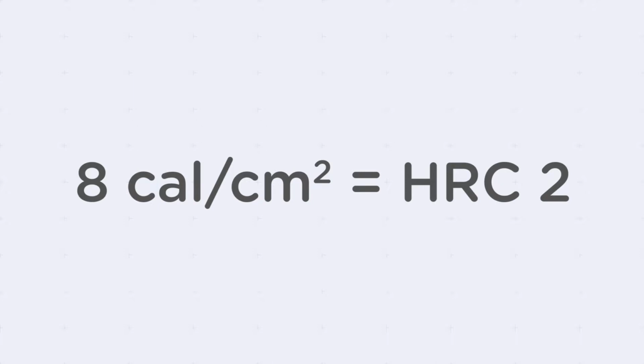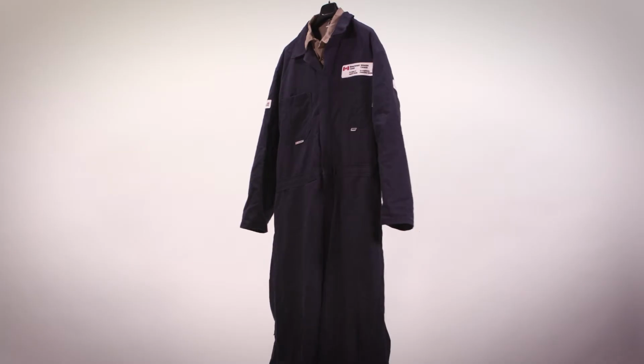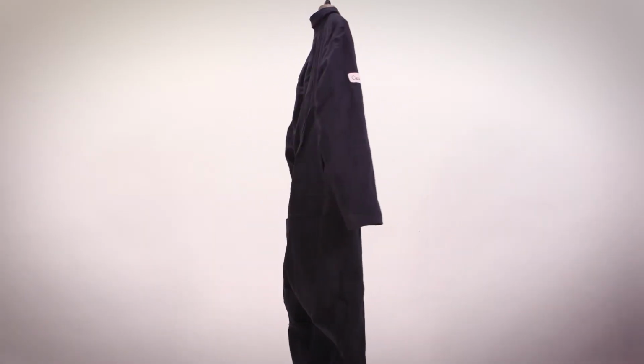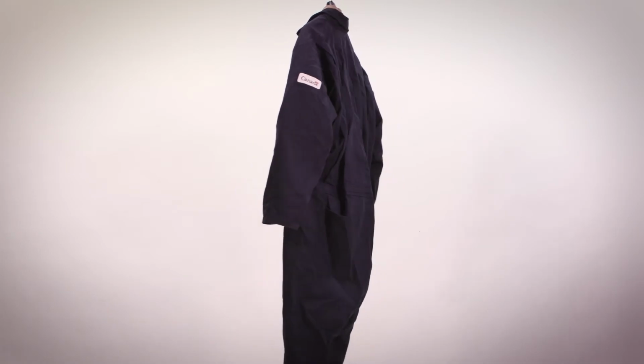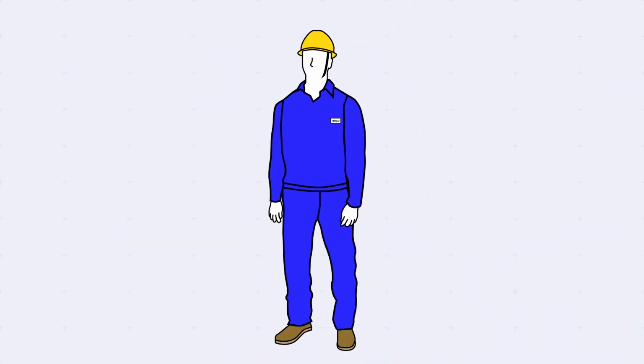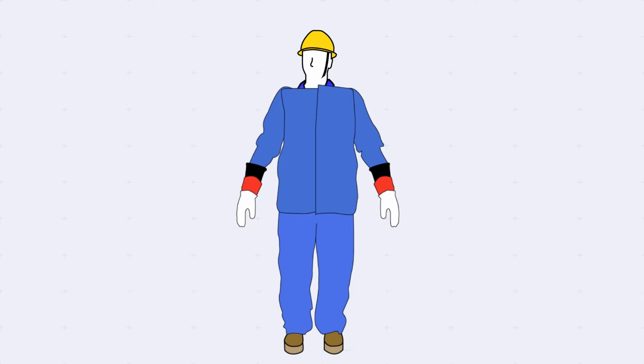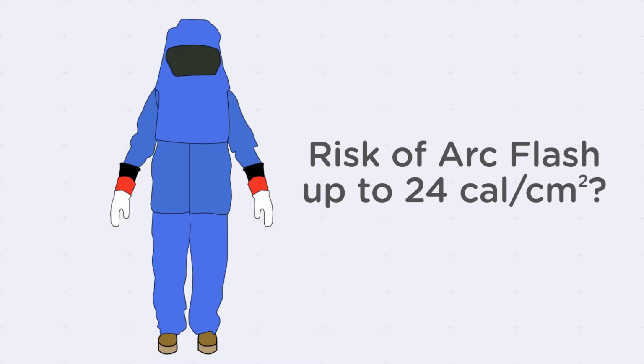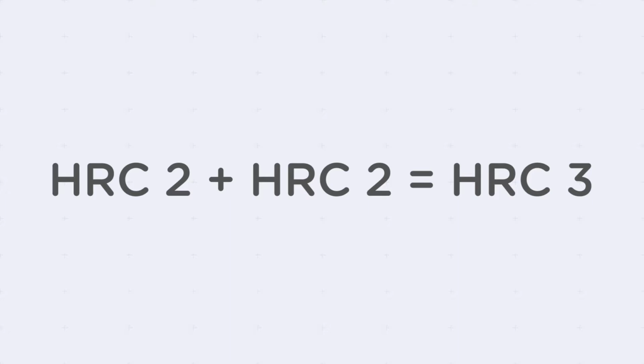This clothing will include HRC 2 rated pants, shirts, and jackets or coveralls. Measurement Canada inspectors shall be provided with HRC 2 rated coveralls. Employees required to perform measurements on electricity metering equipment or witness utility personnel taking measurements that could result in an arc flash level up to 24 calories per squared centimeter, or Category 3, shall be provided with an additional pair of Category 2 coveralls. This additional pair of coveralls shall be worn over the first layer of HRC 2 rated clothing to achieve Category 3 level protection.